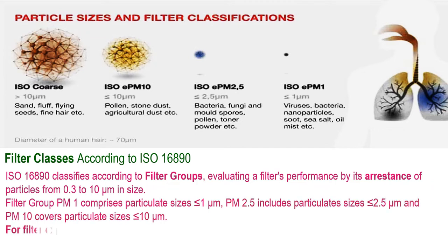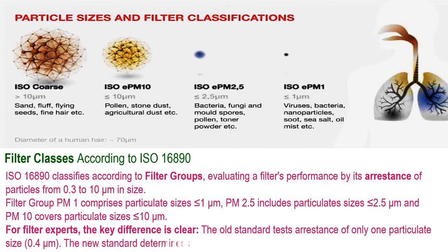Filter classes according to ISO 16890: ISO 16890 classifies according to filter groups, evaluating a filter's performance by its arrestance of particles from 0.3 to 10 micron in size. Filter group PM1 comprises particulate sizes less than or equal to 1 micron. PM2.5 includes particulate sizes less than or equal to 2.5 micron. And PM10 covers particulate sizes less than or equal to 10 micron. The old standard tests arrestance of only one particulate size — 0.4 micron — whereas the new standard determines arrestance over a spectrum of particulate sizes.